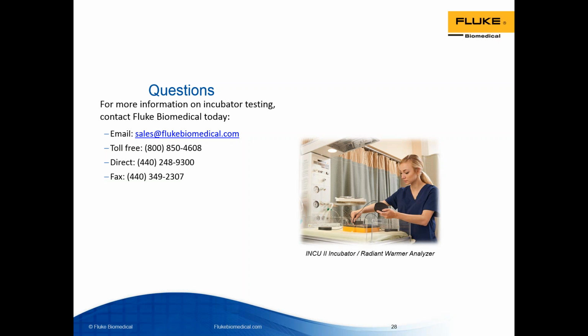So what it does is it will ask you how long does it take you to currently test an incubator or radiant warmer with your current procedure and the tools that you use. Combine that with the visual checks, combine it with the electrical safety, everything that the manufacturer says and what you're currently doing. How long does that take you? And then there's another portion where it says, okay, using this device, with the same things being tested, this is the time difference. And often the time difference is very significant.